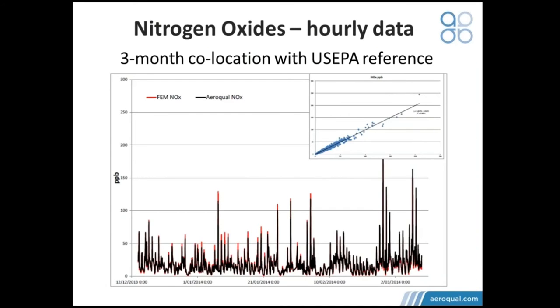This was the data we received back from the independent assessor. In red you can see the federal reference method, and in black the Aeroqual module performance, over a period of 3 months. You can see in the correlation ratio that there was a very high statistical correlation of the data. Bear in mind, being a US EPA reference station, it was calibrated every month by contract with the government, whereas the Aeroqual station was not calibrated at all, apart from a factory calibration before installation. So over a period of 3 months, there was minimal drift, and that was without a field calibration of the instrument.